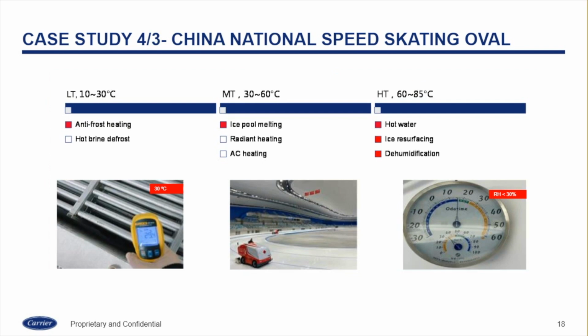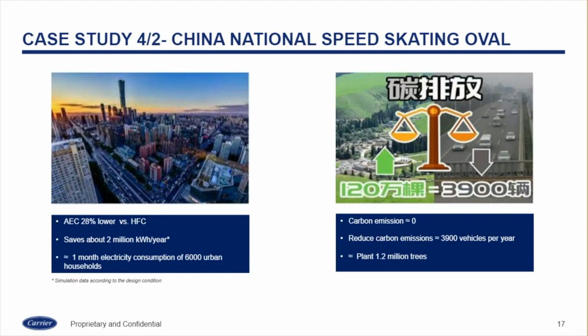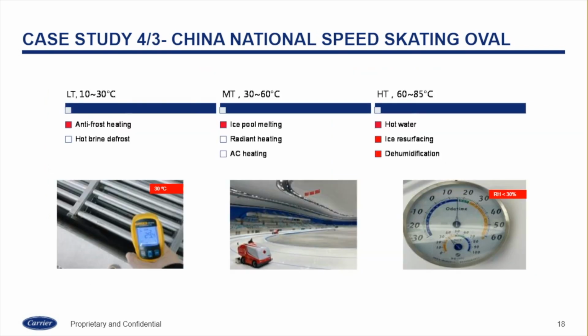Next page, please. This is a quick guide to the heat recovery application for this case. As I just mentioned, the CO2 system has very good heat recovery, covering different temperature ranges and a very big amount of heat capacity. This is exactly the heat recovery application in this case. We have the lower temperature range of 15 degrees for anti-frost heating of the ice rink, and the middle temperature of about 30 degrees for the ice pool to melt ice. For the high temperature range, 85 degrees is for hot water, ice resurfacing, and dehumidification. So that's it for the high side of the application.